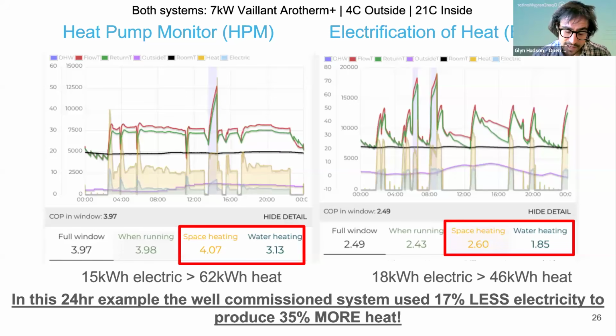So it resulted in the well-commissioned system on HeatPumpMonitor using 17% less electricity to deliver 35% more heat. So that's quite substantial. But the good news here is this is just control settings that caused this. So it should be relatively easy to fix if this had been picked up. And this is where monitoring can really help to visualize what's going on and see that there is an issue like that.